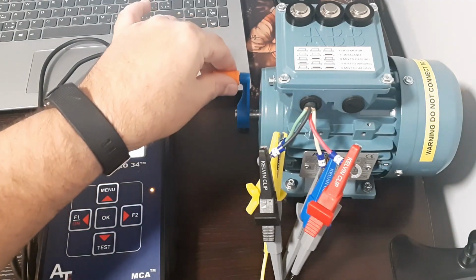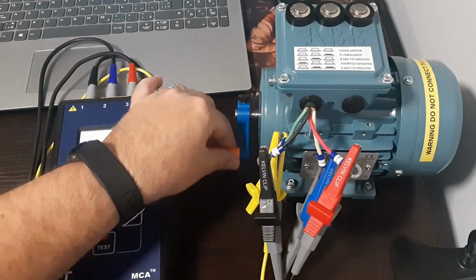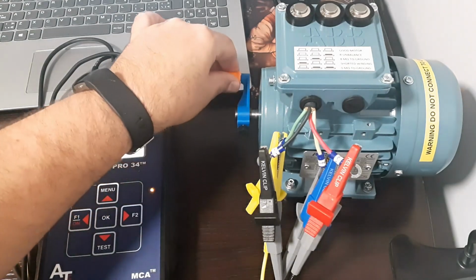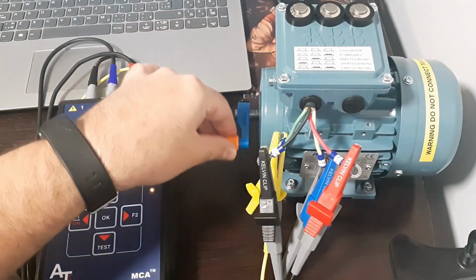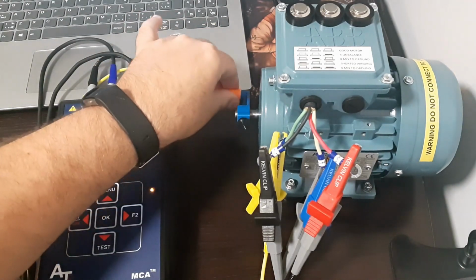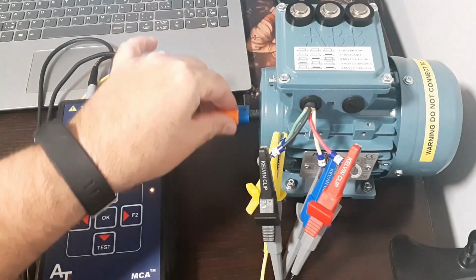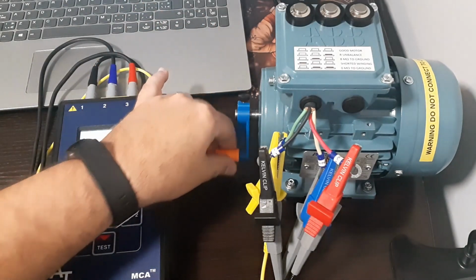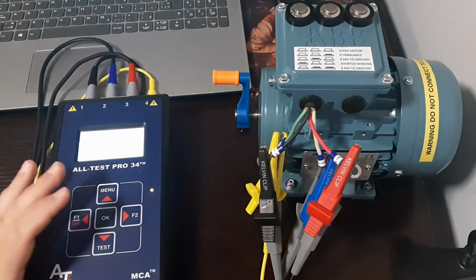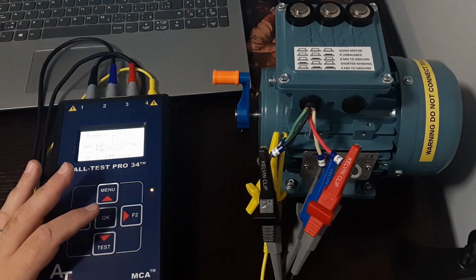Now this is a type of testing you can do out in the field where you have to gain access to the rotor. You don't necessarily have to do this dynamic test, but it gets you more information. And it's also a great test to do on your motors that you're about to install to make sure that you haven't gotten a dud motor.